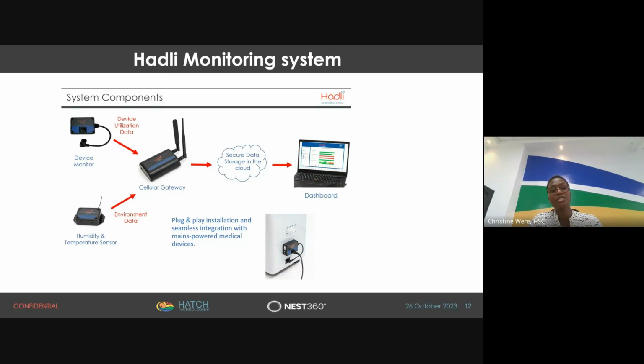We have a gadget called a device monitor, very small, like the size of a mouse. This device monitor attaches to the device. Let me use the pointer, I hope you can see this concentrator in the last image, this is how the monitor is attached to a device. You connect it to the power input part of the device, then from the monitor port you connect the device directly to the socket. So this is how the device monitor looks on an oxygen concentrator, and how it has been connected.